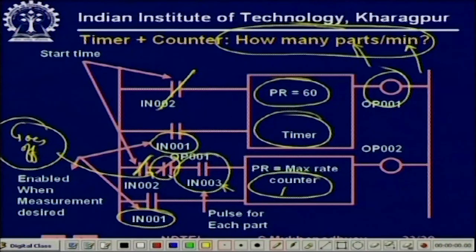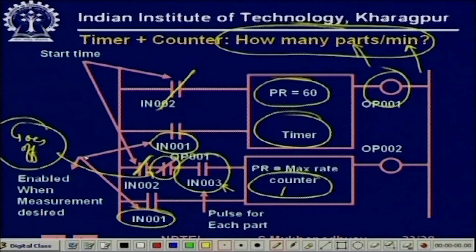When this goes to 0, this becomes open. Whether a pulse comes or not it does not matter — this cannot be 1 because these are in series. Therefore at that time, in the counter you have the value of how many parts have passed over the conveyor in the last minute.